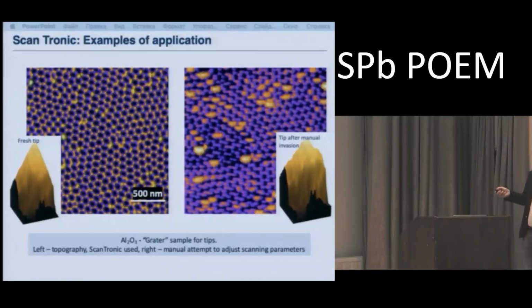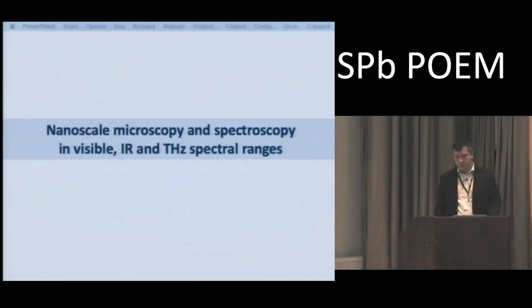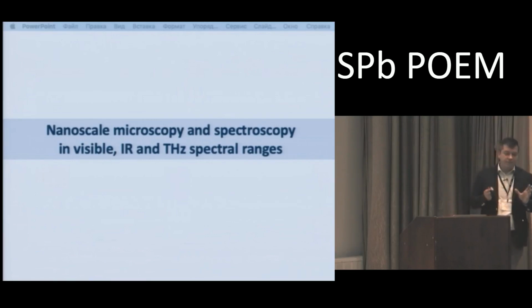Another example is the aluminum oxide, which is actually the grater for the tip. This is an automatically made image, and this is the image made during manual adjustment of parameters. At the end of the scan, the parameters are adjusted and are quite correct, but during this adjustment process the tip is already damaged, and one has to exchange the tip.